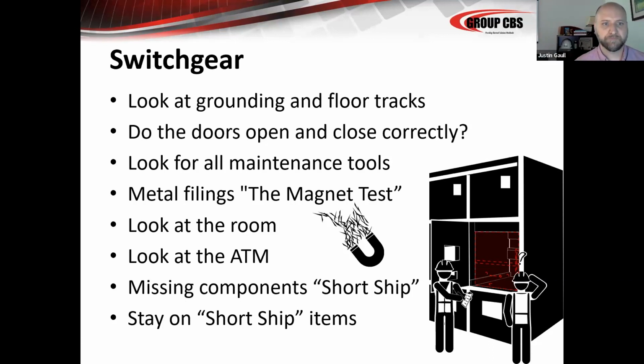And in ATS testing, you have more time to do it. So there's no reason not to push. In maintenance testing, you're up against the clock. So you have to propose a plan in maintenance testing that gets as much done to get as much sense of reliable service as you can based on the time they'll give you. And acceptance testing, quite often you have plenty of time. So there's no reason not to push primary current and check the current transformers, make sure they're not jumpered out, make sure they're connected correctly, push primary current through everything.